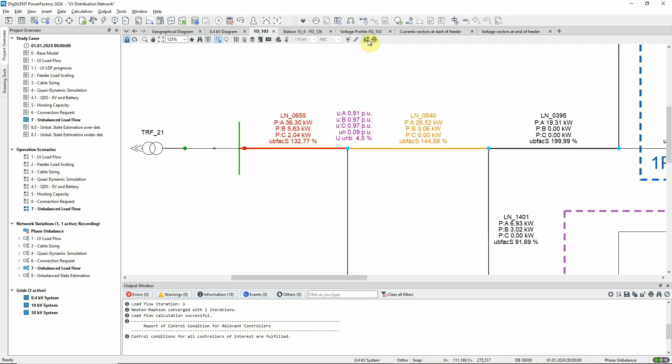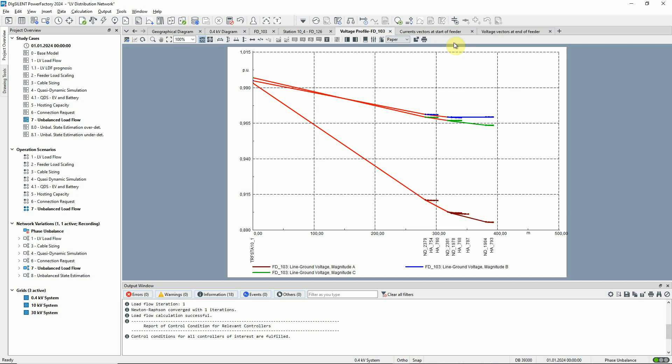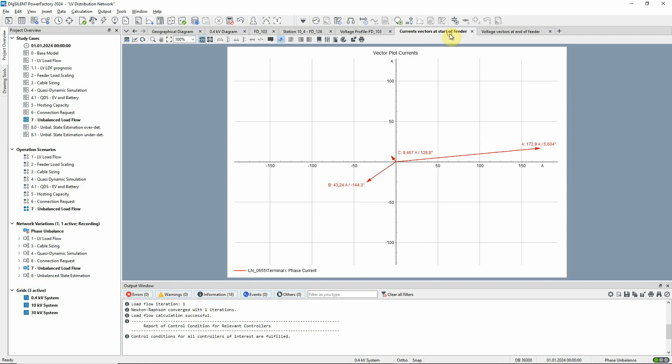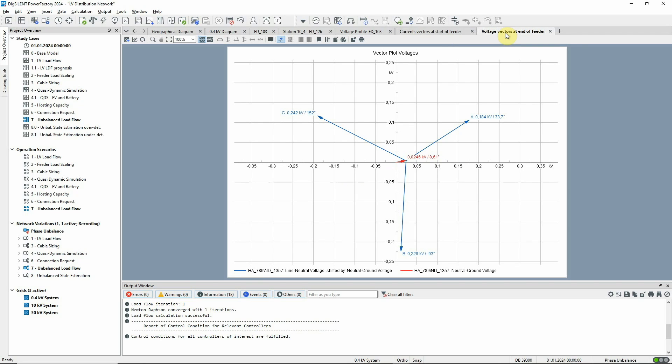The imbalance is reflected in the voltage profile. The voltage differences are very high and some of the lines are loaded above their 80% upper limit, as indicated by the red colouring. Looking at the vector plots, it's clear that the currents are very unbalanced, and there's also a high neutral to earth voltage.